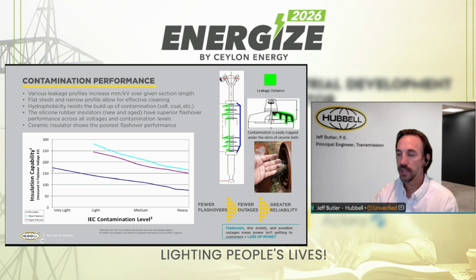And then the bottom line is a porcelain bell string, and basically what we saw is across the full range of contamination, we saw superior flashover voltages on the polymer insulators than their porcelain equivalents. And these were equivalent leakage distances. So we matched the leakage distance of the ceramic string to the leakage distance of the polymer insulator, and we saw higher flashover voltages. Now, what does that mean? That means you're going to be able to get increased flashover protection, which in the event of an overvoltage or some kind of event on your line, you'll have greater protection, leading to fewer outages, which is then greater reliability for your line, which means it keeps the meters turning, the lights on, and end users happy.